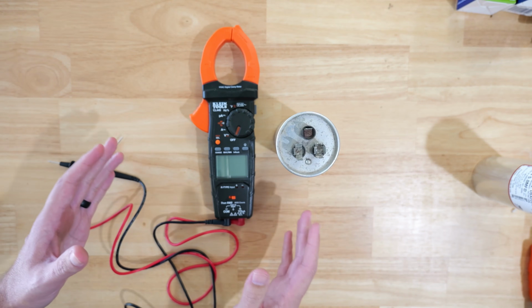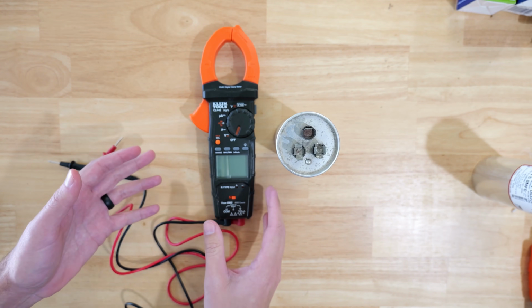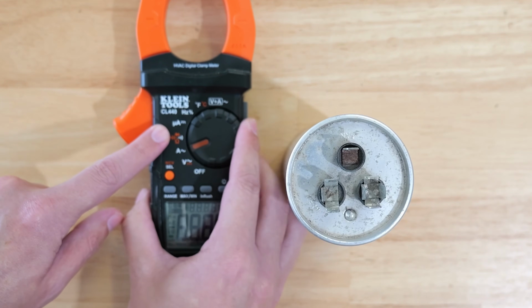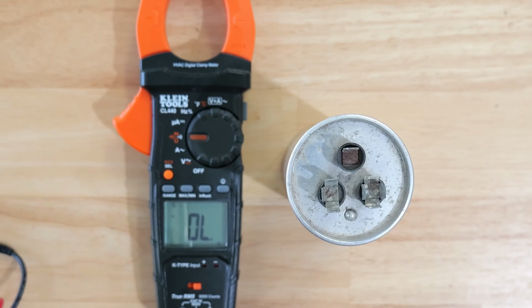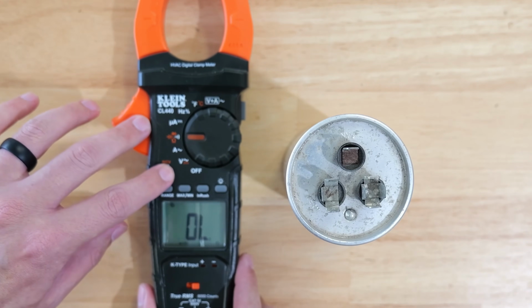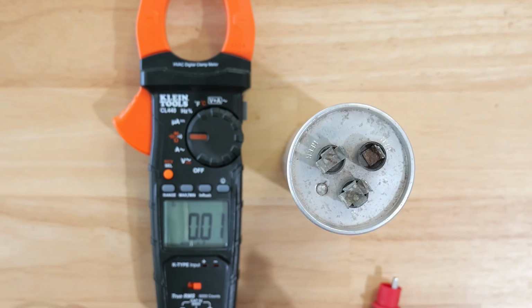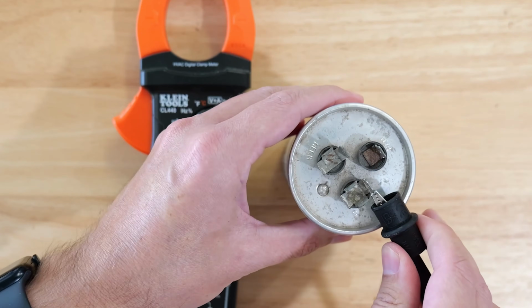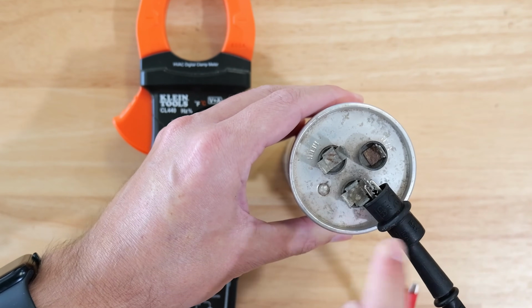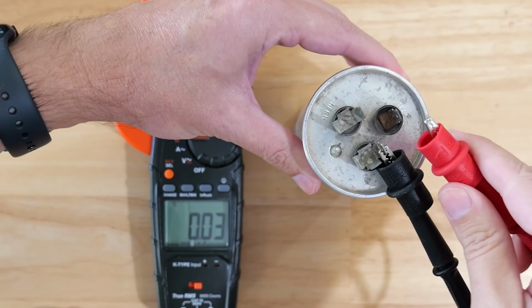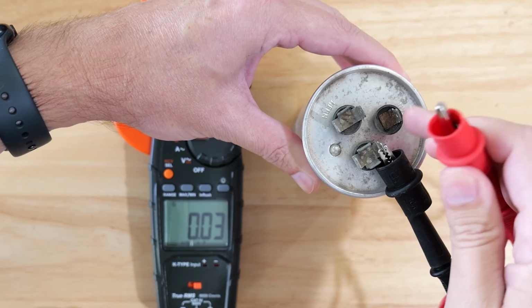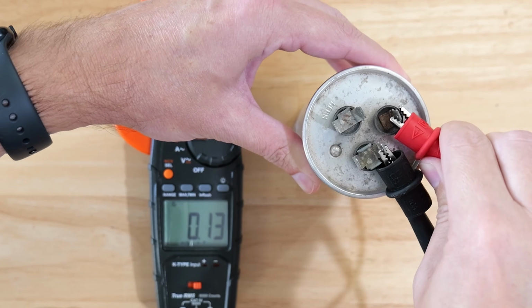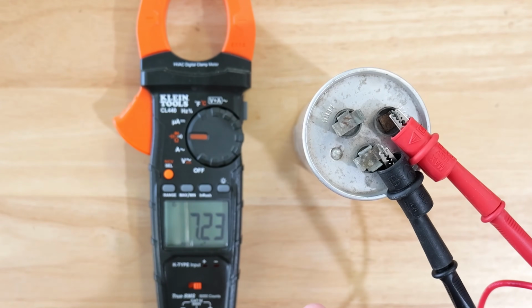All right, so the first thing I want to do is get my multimeter set up again. Again, all I'm going to do is set it over here to this setting, which has continuity, it has resistance. Just going to change the settings to where we can read microfarads. All right, so first one I'm going to check is I'm going to connect my first probe or alligator clip down here to my common terminal. Then I'll take my second probe or clip and connect it to my fan terminal up here. And again, we should be within around 6% plus or minus of 5 microfarads.